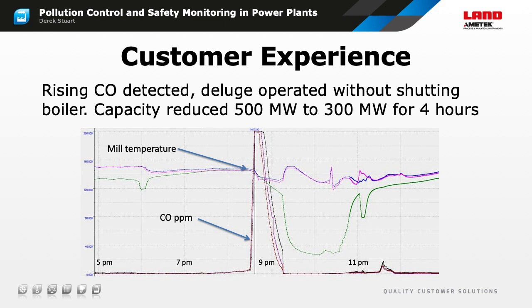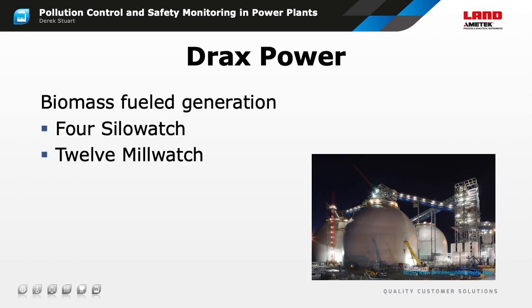Drax Power Plant in the UK was at one time Europe's largest coal-fired power plant, with 6 650 megawatt generating units. Over the past 6 years, they have converted 3 units to run entirely on biomass, with a 4th conversion recently completed. The pellet fuel is stored in 4 huge domes, each measuring 50 meters high. They use both Land CO monitors and our HotSpotIR line scanners to monitor the condition of the fuel within the plant, and this has helped them to maintain their excellent safety record.